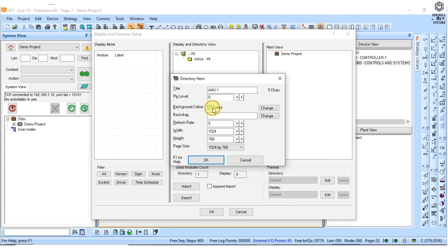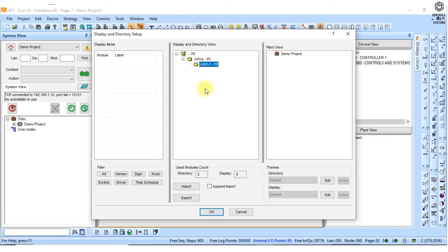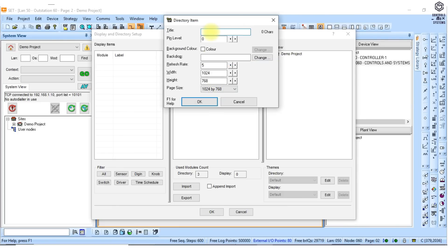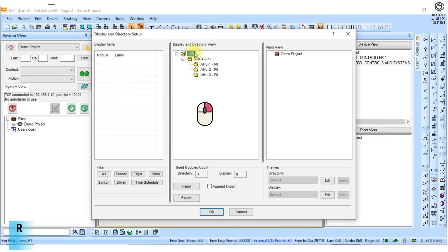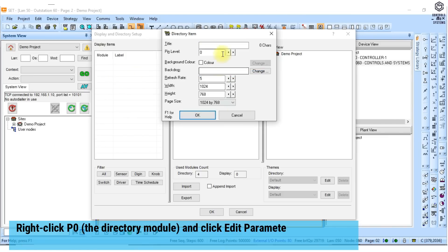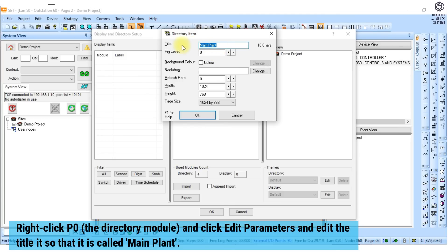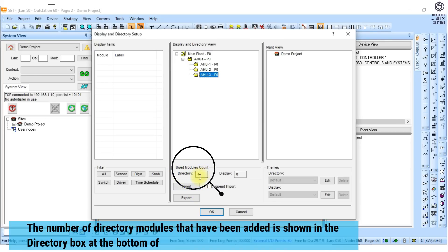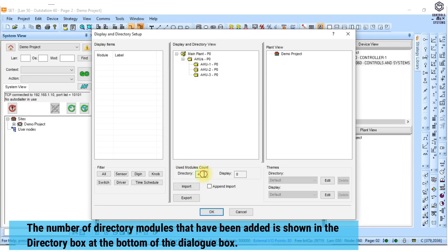Now add another directory module called AHU1 one level down in the hierarchy by right clicking the directory module you have just added — AHU — clicking insert directory, and entering the name of the module. Leave the pip level at 0. Repeat the process to build up the hierarchy. Right click p0, the directory module, and click edit parameters and edit the title so that it is called main plant. The number of directory modules that have been added is shown in the directory box at the bottom of the dialog box.